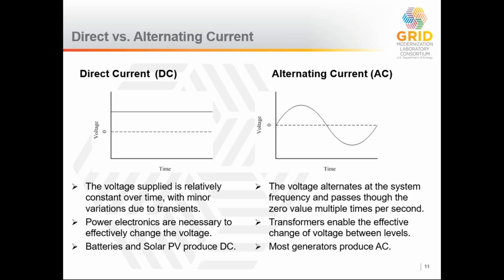With alternating current, you can generate power at around 20 to 30,000 volts. However, you can't move it very far at that voltage. So it's generated at that voltage, stepped up to 230, 500 in the Northeast, up to 765,000 volts. It can be transmitted long distances and then stepped down to distribution level voltages. That ability to cost effectively change the voltage is what makes alternating current such a common use today.